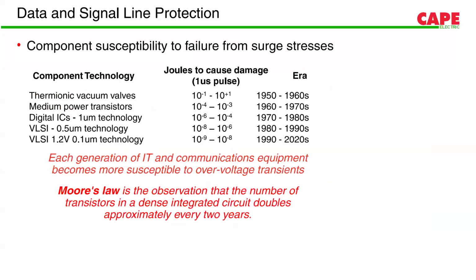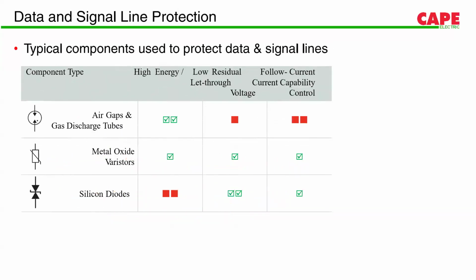So this is an example. In the 1960s, a normal component could withstand up to 10 joules of energy, whereas now in the 2020s, we are in 2025, mid of the 2020s, this has reduced drastically. A single VLSI component can withstand somewhere in the range of 10 to the minus 8 joules of energy. So there are generally three components used inside a communication SPD: gas discharge tube, metal oxide varistors, and diodes, sometimes also called transorbs.